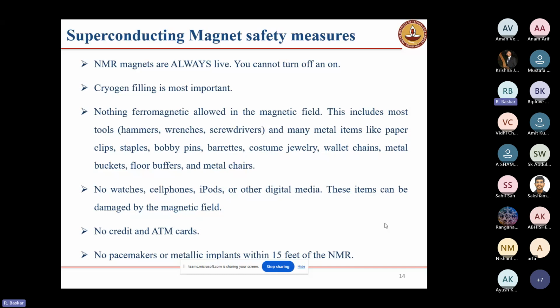So no ferromagnetic or magnetic materials are allowed inside the NMR room. Since it is shielded, only a small leakage will be there. Up to 2 meters, we can feel the 50 Gauss magnetic field, depending on the magnet. Generally, the 50 Gauss can be felt up to 1 meter, but some leakage is there, and it can be more. That's why we should not keep any magnetic material inside the NMR room. No watches, no cell phones, no iPads, nothing is allowed inside the magnet NMR room.